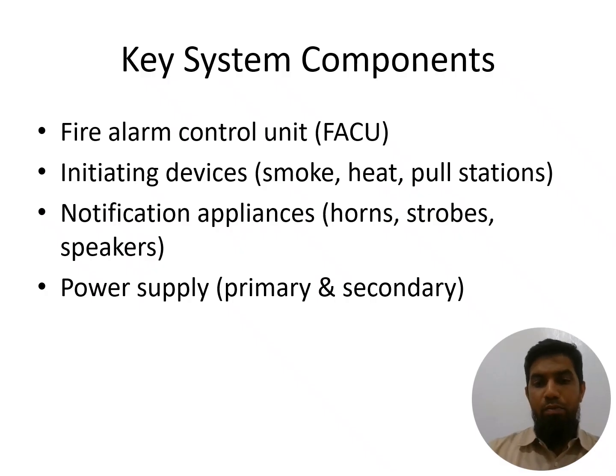Fire alarm control panel. The fire alarm control panel is the brain of the fire alarm detection system. It monitors all inputs such as manual and automatic detection and activates output devices such as horns, bells, strobes, and other building controls. There are two types of fire alarm control panels: one is conventional and the other is addressable.